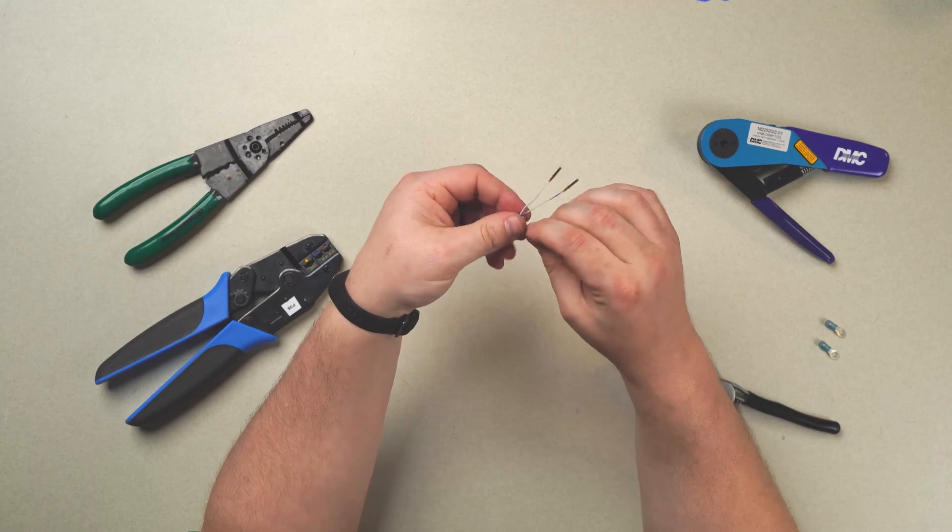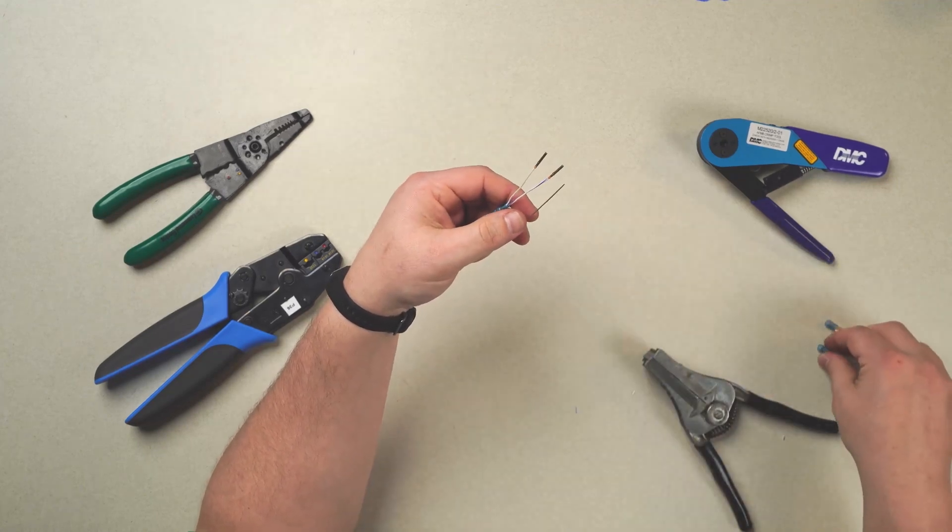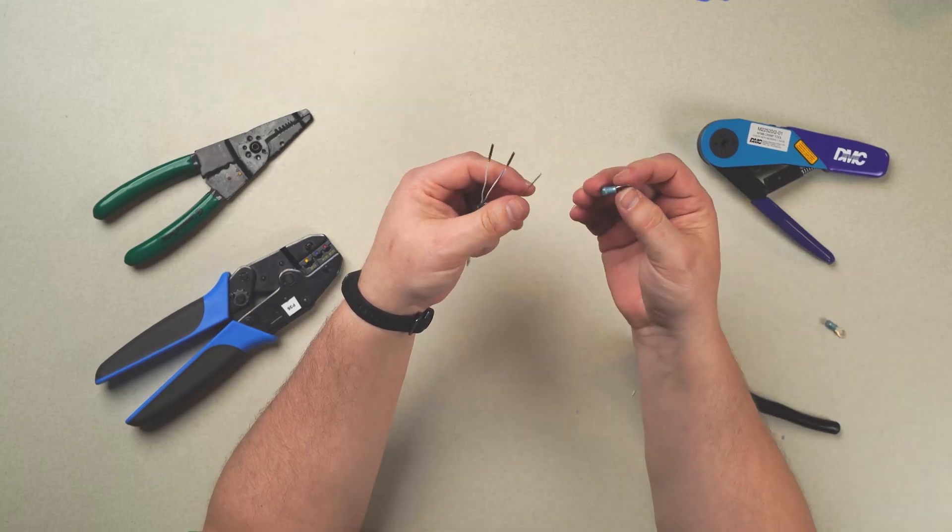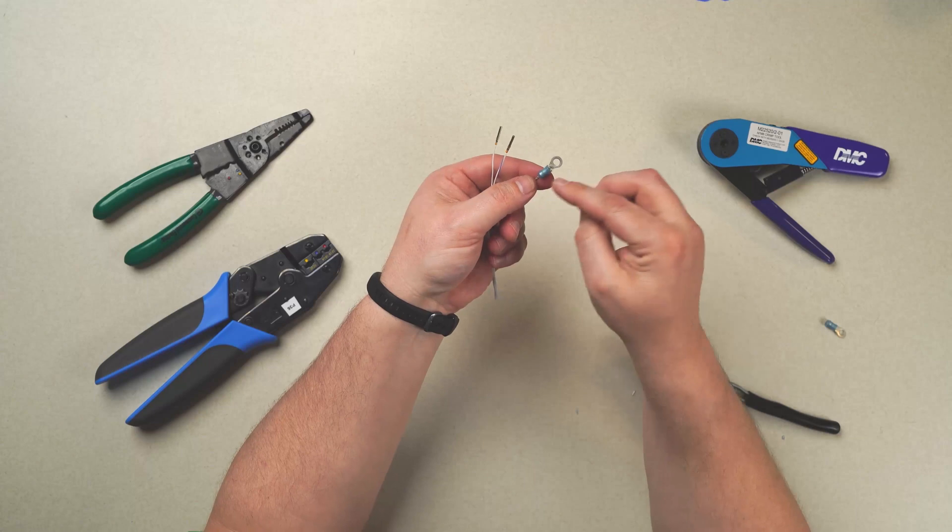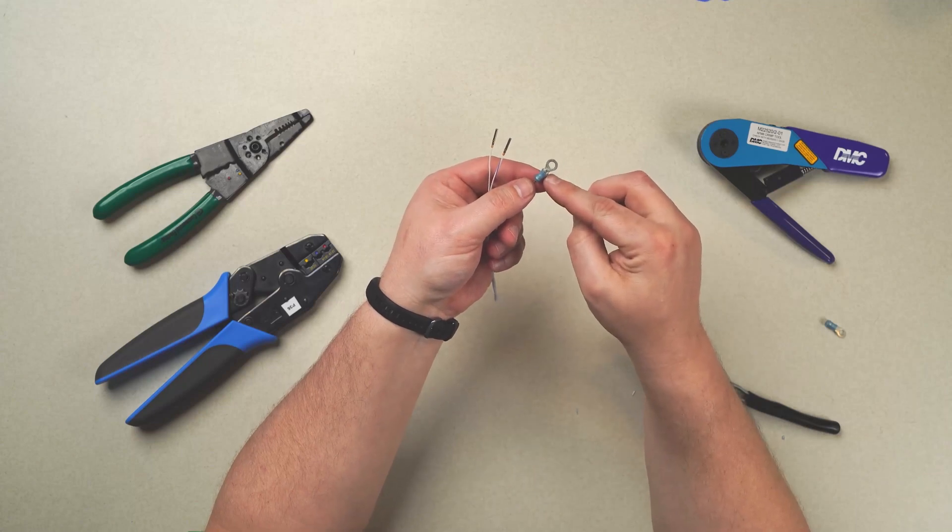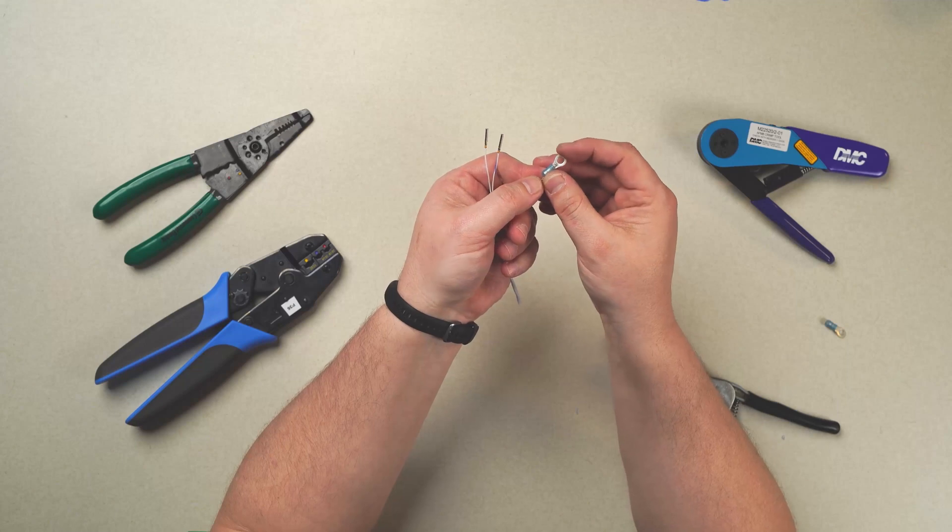Next, let's go ahead and crimp on our shield termination. First off, we're using the appropriate size. We want to make sure that we see exposed shield through the actual ring terminal itself. You see it goes all the way through.